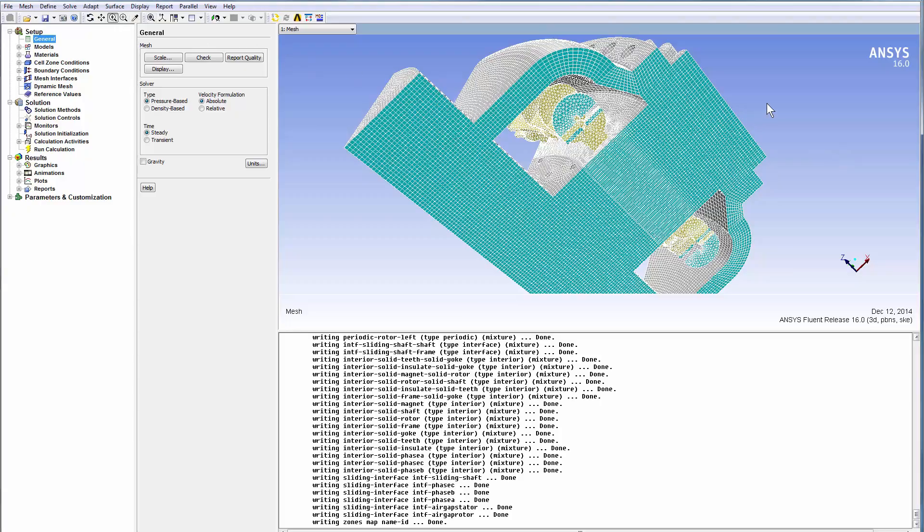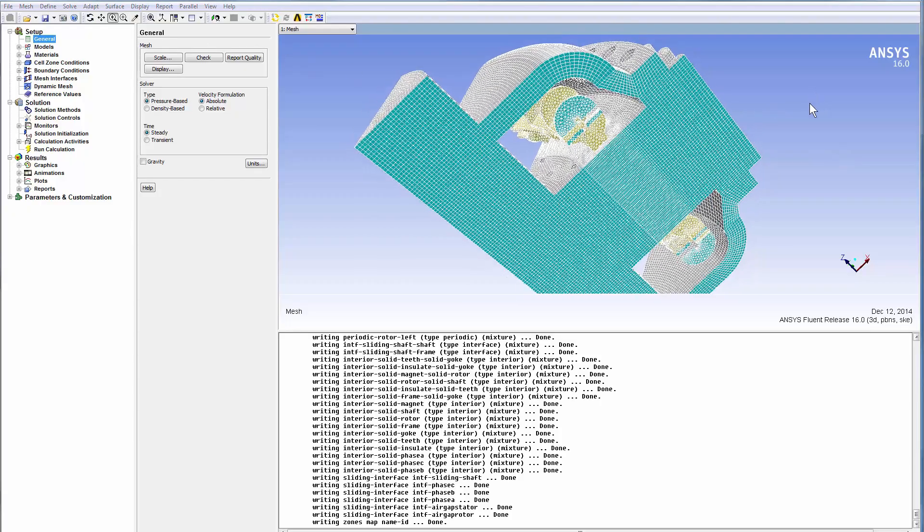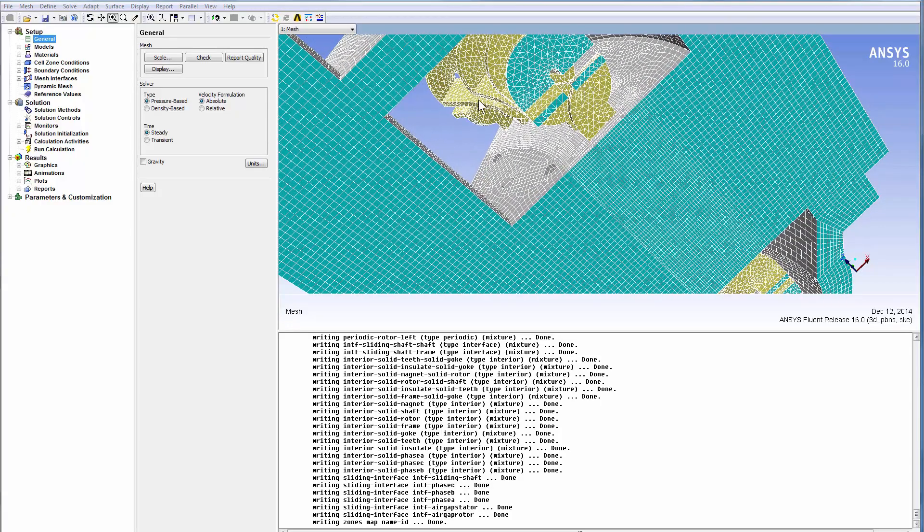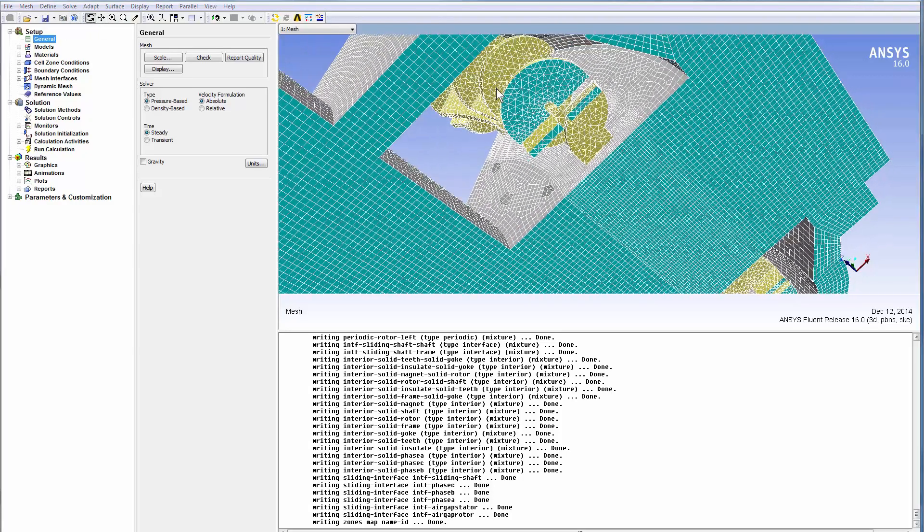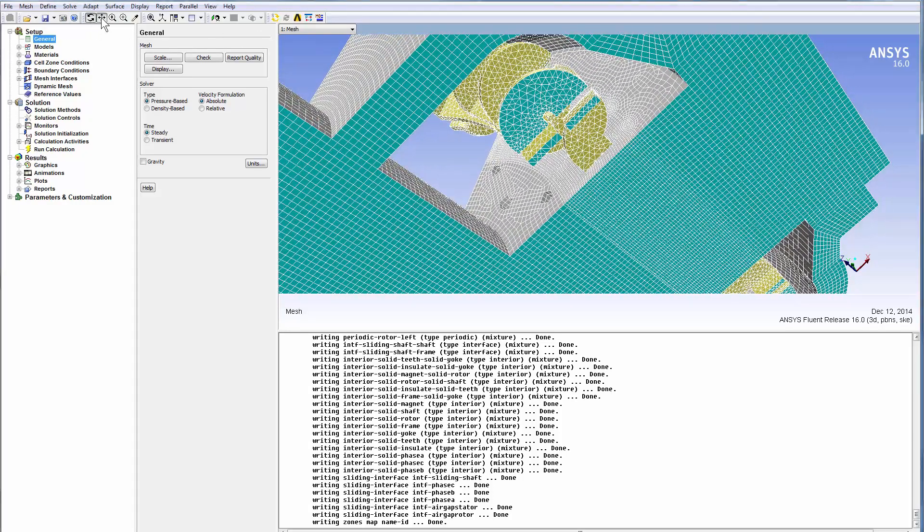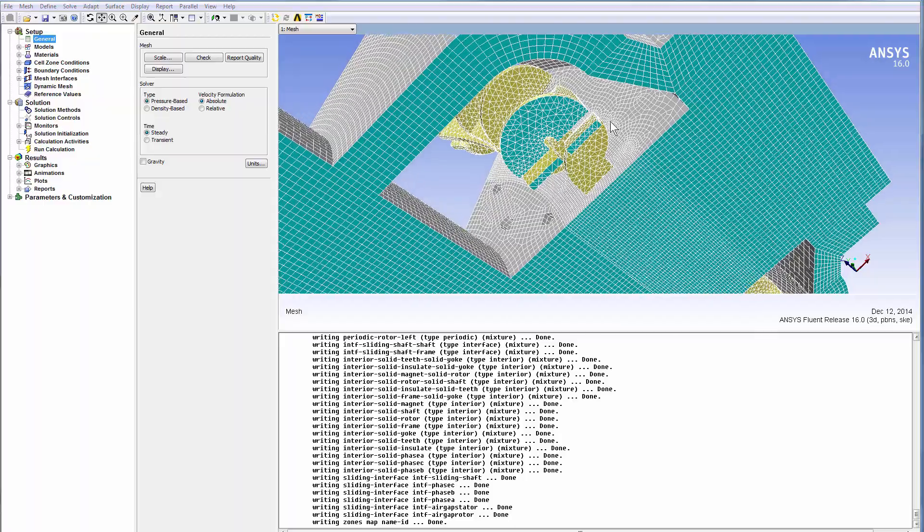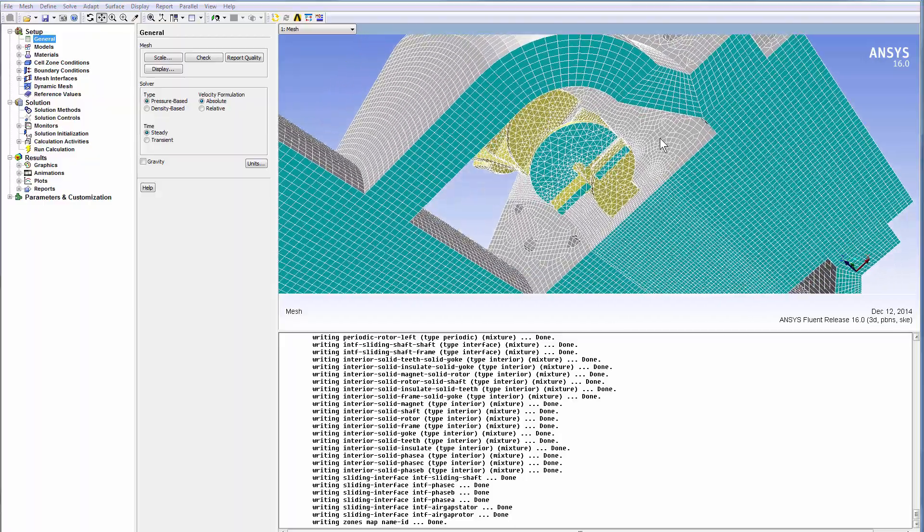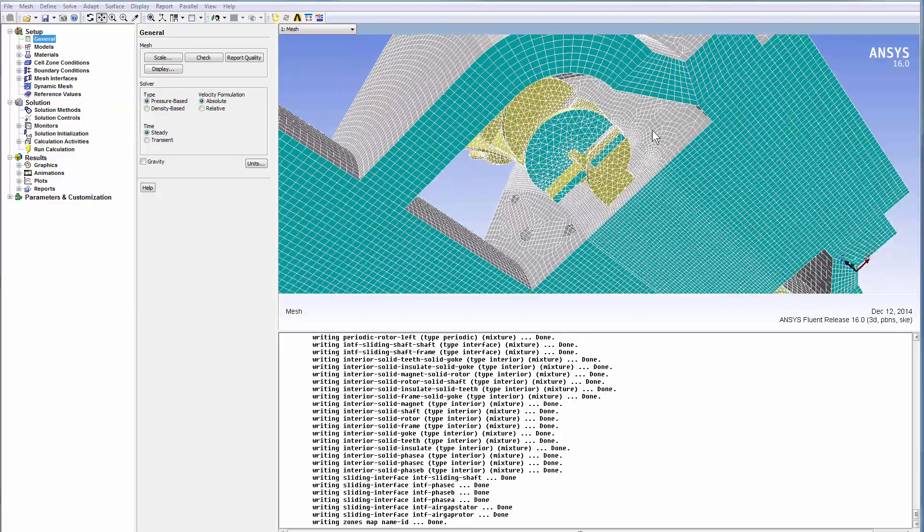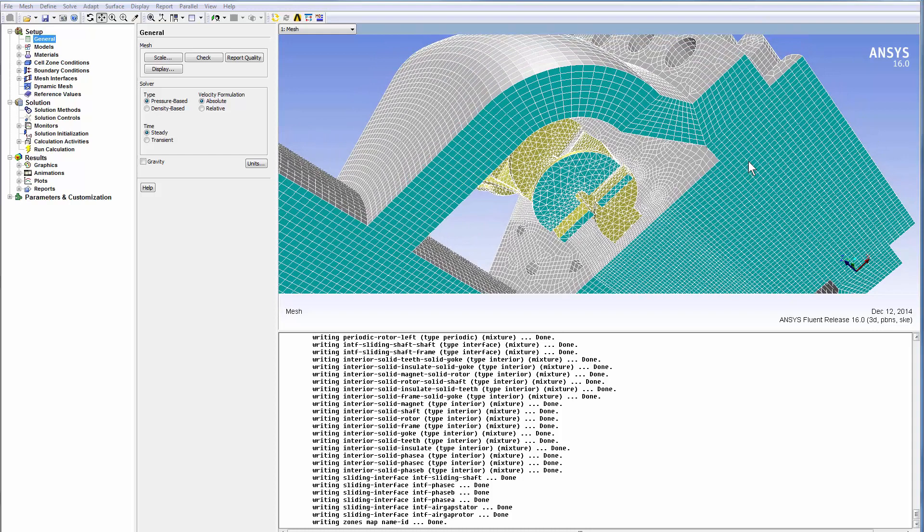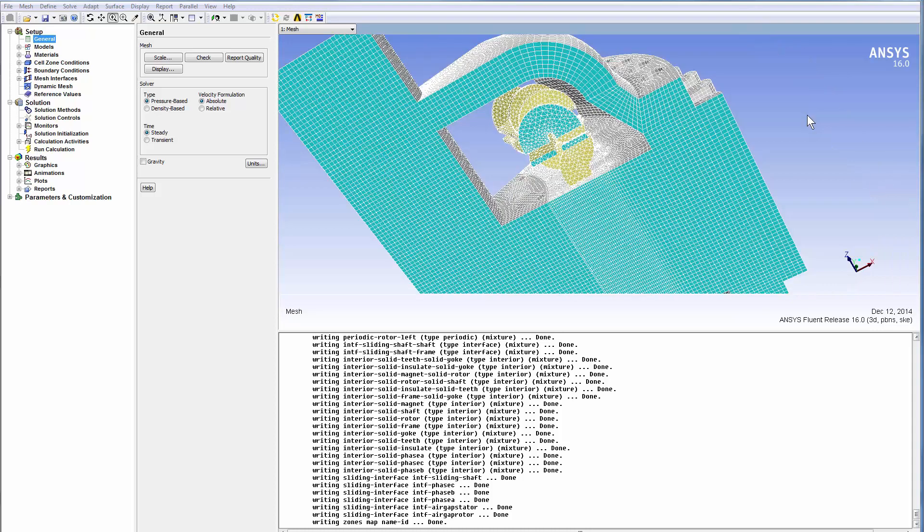The end windings are in open air. They transfer the heat by convection. The parameters of conduction and convection are dependent on the cooling system. The holes in the back iron can be used to enforce liquid cooling. Later, the CFD environment provides you the capability to establish multi-flow conditions on these holes.